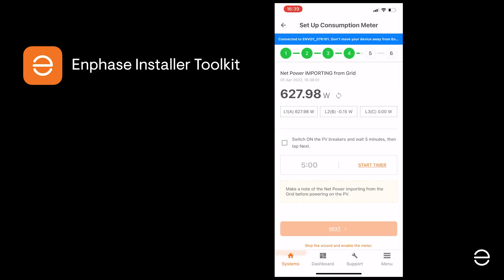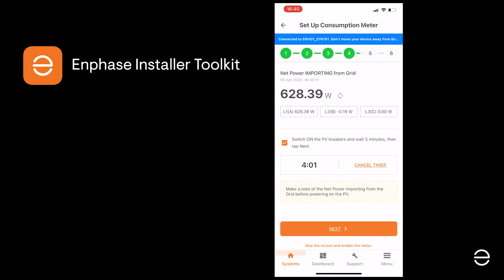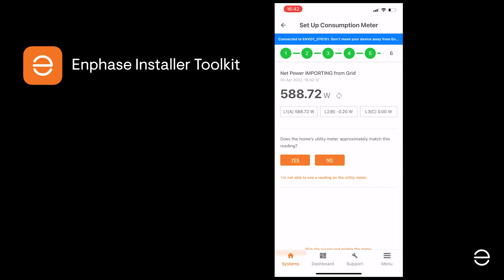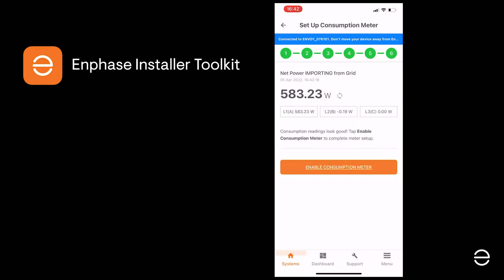Once you're happy the load is correct, the next step is to switch the PV system back on again, so you're adding PV production. You'll need to wait at least five minutes for it to start production, then check if the consumption load starts going down as expected. There's a timer you can start to help check the five-minute wait period. As the timer counts down, you should see that the consumption load — the power being pulled off the grid — progressively decreases as electricity is used from the PV system. In the case of a larger PV installation, you may even see the reading move from importing power from the grid to exporting it. Once you are happy with the readings, click Next and confirm that they are correct. You can then enable the consumption meter.